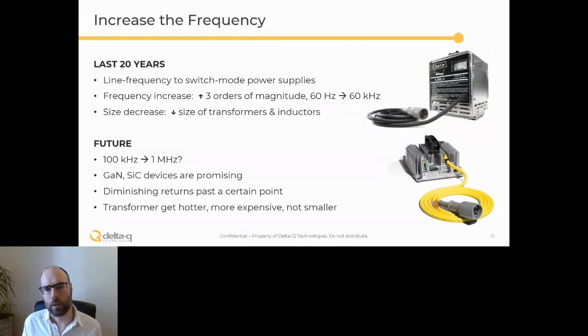That's why with those old ferro-resonant chargers, like the photo at the top, half of that box and almost all of its weight is taken up by a very large 60 hertz steel and copper transformer. Whereas the charger below it is the one now used in the field, and its actual transformer is about 100 grams.